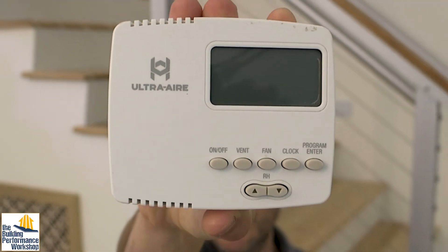The humidity controller that Ultra Air offers is mountable anywhere. I could have put it up with the rest of my array of sensors for heating, cooling, ventilation, and monitoring equipment. I opted to put it inside the return plenum for ease of wiring and to keep the number of sensors in my space to a minimum. I'm aware that might result in a slightly different reading since it's inside a steel box, but all I have to do is monitor the humidity out in the space and set the sensor to activate at a set point that makes sense with what I'm reading. If I'm at 40% out here but the sensor says 45%, that's fine — I just care about maintaining the humidity I'm looking for.